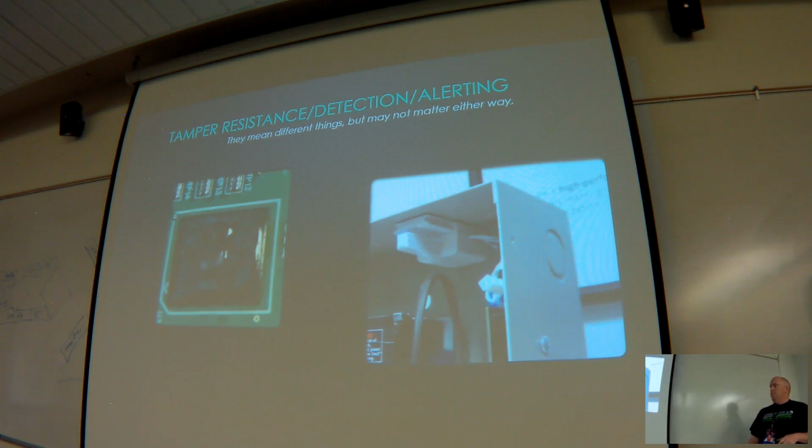They were a little bit perturbed that they didn't know the alarm was going to go off, and I told them this scenario where we sat there over coffee and pressed it until they called us. And then they immediately went and fixed that problem. They had no idea the tamper switch never actually got activated.